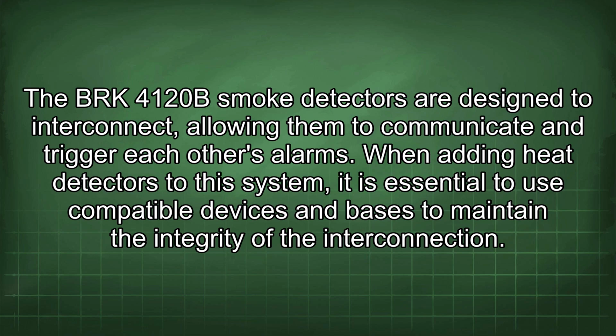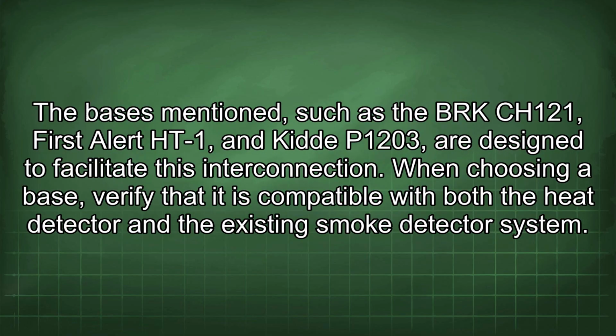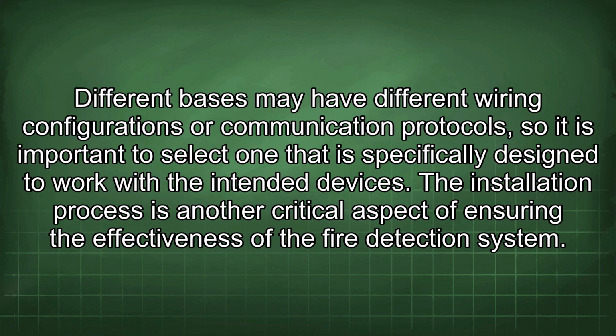The BRK4120B smoke detectors are designed to interconnect, allowing them to communicate and trigger each other's alarms. When adding heat detectors to this system, it is essential to use compatible devices and bases to maintain the integrity of the interconnection. The bases mentioned, such as the BRK CH121, First Alert HT-1 and Kidde P1203, are designed to facilitate this interconnection. When choosing a base, verify that it is compatible with both the heat detector and the existing smoke detector system. Different bases may have different wiring configurations or communication protocols, so it is important to select one that is specifically designed to work with the intended devices.